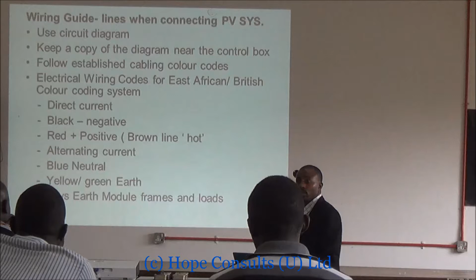So how do we do some checking and inspection? After the electrical connection and with loads off, we check the connections again: the nut you are supposed to put, the other part of the connection. Look at the charge controller, whether the wires are all well put. Make sure that they are firm and properly connected as per the wiring diagram. Be keen to find any loose ends. Try to touch and see. Test the current continuity in all connections.